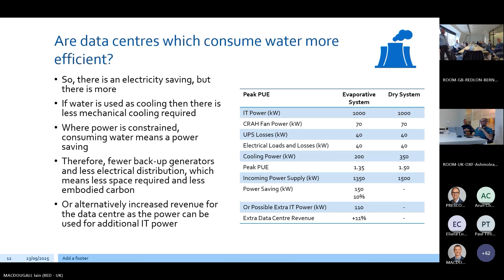In terms of water use, is it more efficient to evaporate the water at the data center? There's an ASHRAE journal published in November 2022 that looked at water consumption for a 1,500 kilowatt data center in 3 US locations: Denver, Phoenix, and LA. As we expected, and as we've shown before, there's an energy reduction over the year of approximately 65% by evaporating water.